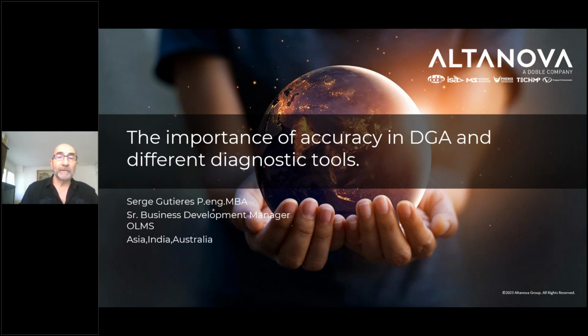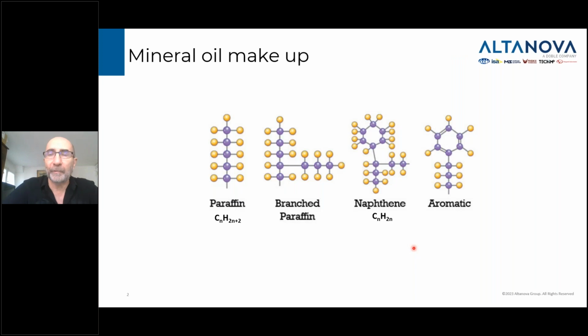Good, so let's go over a brief review of why we do DGA. As you know, our transformers are using oil. Mostly 95% of transformers are using mineral oil around the world, mostly for two reasons. One, to use that as a cooling fluid to remove heat from the core. And the second one is insulation. Now, the major oil that's being used is mostly mineral oil, and mineral oil construction comes in mostly different forms.